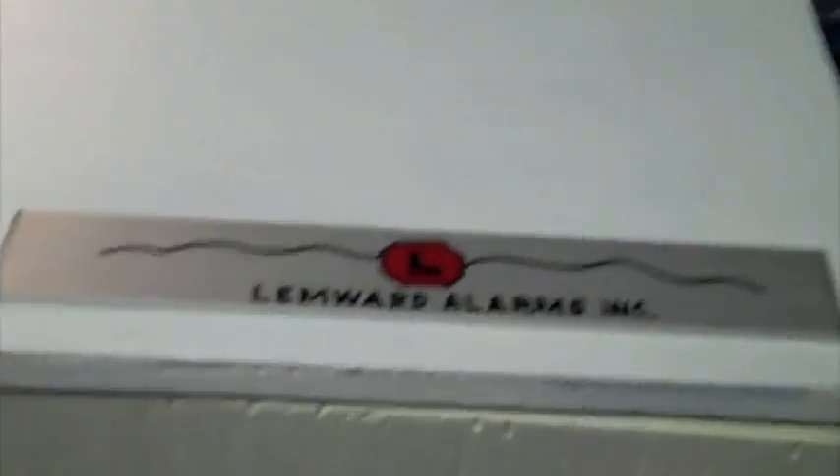Push the silence button — it activates the light and the strobes are flashing while the horns are turned off. Push this to reset, and push this to turn off silence, because if you don't do that and you activate it again it will activate in silence mode — you don't want that happening. Here's the two wires and I just need to connect them together. Now it's in alarm mode. Mess that up, break those connections apart, then reset and turn off silence.